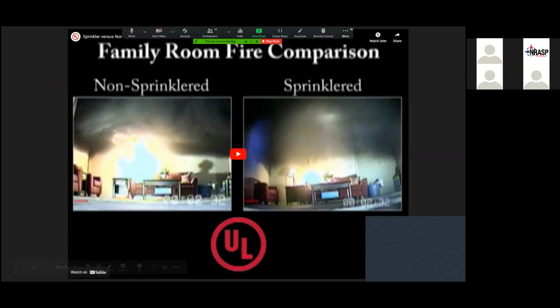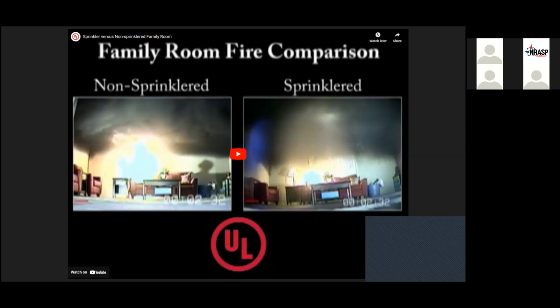Hopefully this video works. It's kind of a long video. There's no audio to it, so you're not missing anything. I'm going to try and push it through, but this shows you the difference between a sprinklered and a non-sprinklered space. This is a test that UL has done. They took 2 identical rooms, built them the same, furnished them the same, started the fire in the same location, and now we'll watch as the fire progresses, and then you'll be able to see that fire sprinkler system activate and how that fire reacts in relation to that fire sprinkler system.